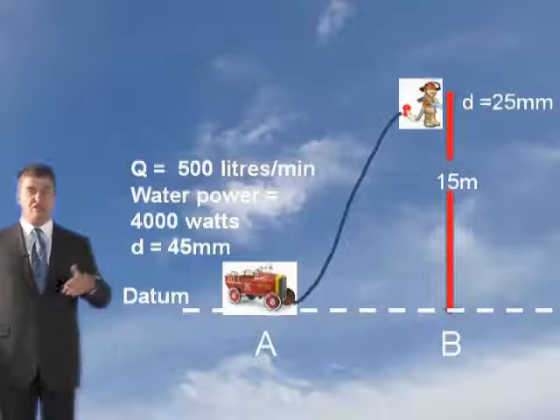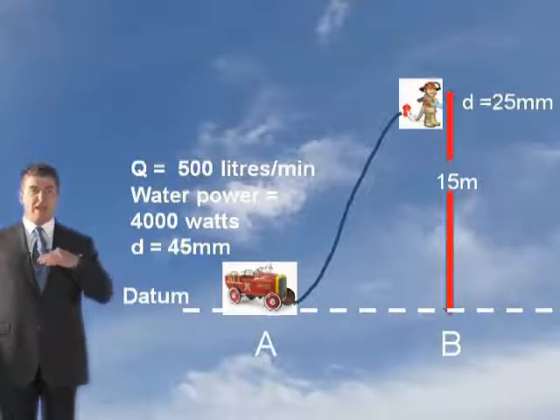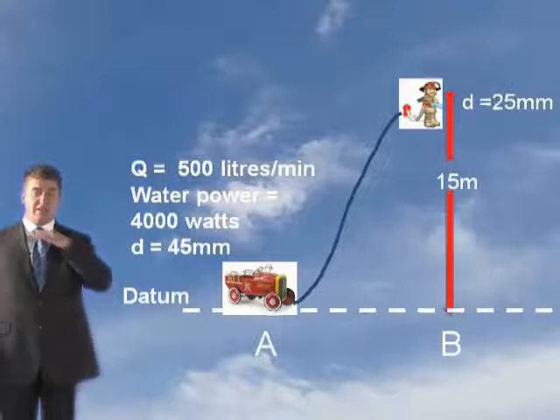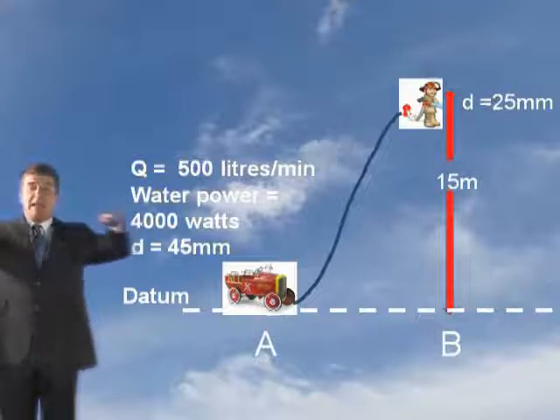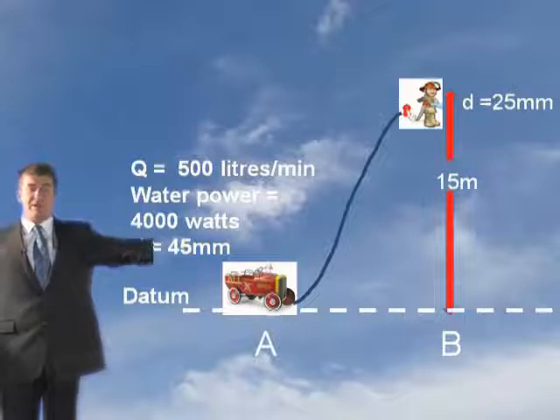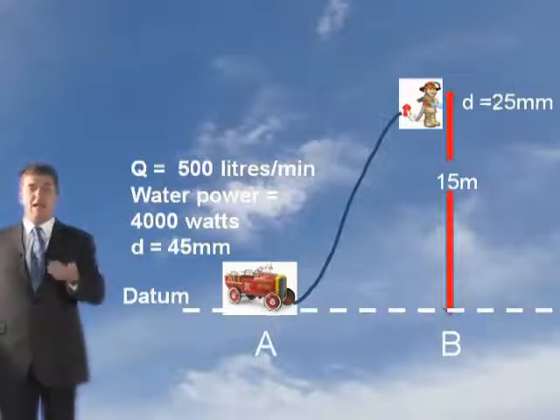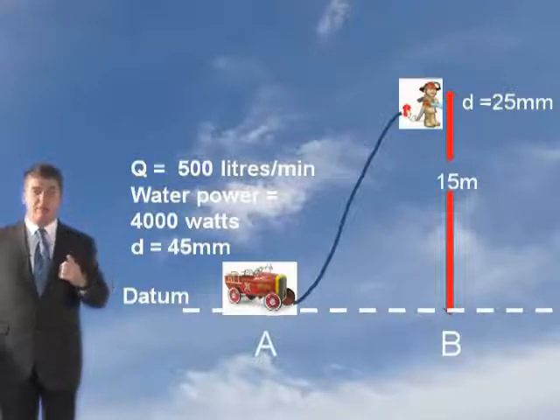What's the first thing you do when working out any Bernoulli's question? First of all you do your sketch. You've got your fire engine, you've got your guy on the branch. You've put your Q in, you've put your water power in, you've put your diameter at the bottom. Your datum line, which is the point you're taking all the calculations from, has got to be level — always flat. It can't be angled because it has potential. You take it at the lowest point of the system, which is at point A. You've put in your height of the guy on the branch which is 15 metres and your diameter, so you diagrammatically draw the problem.